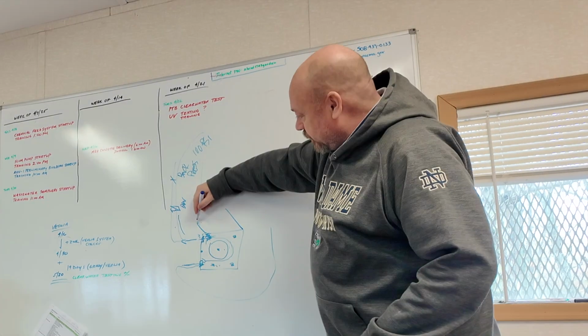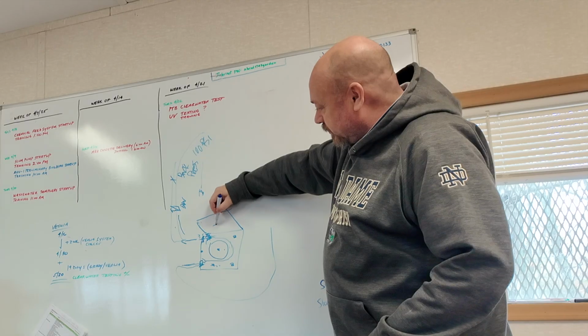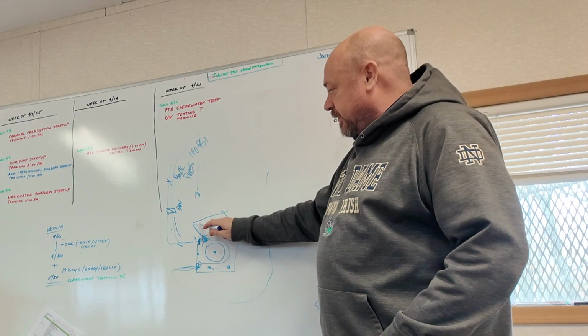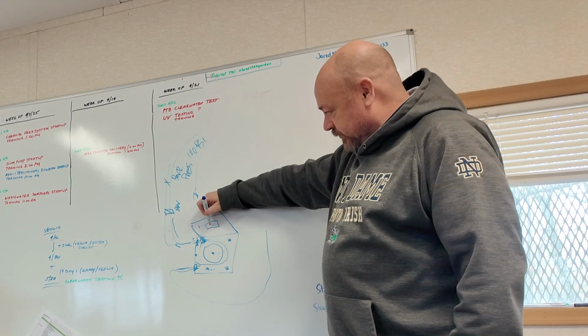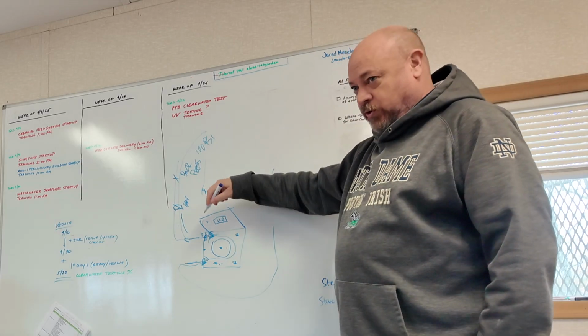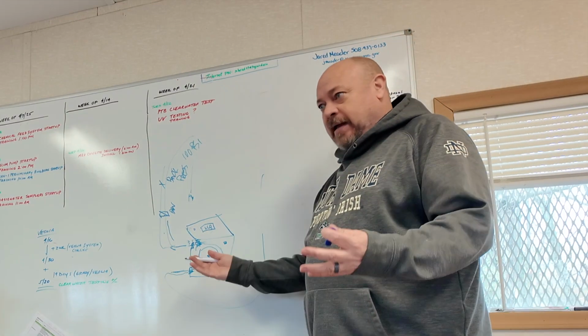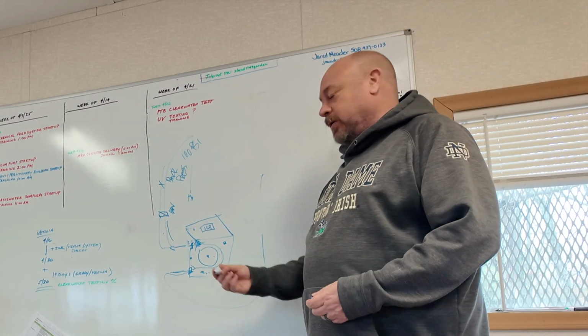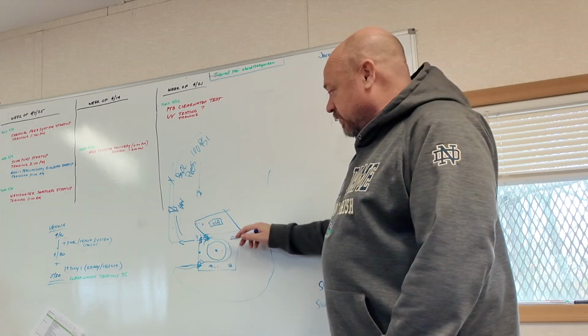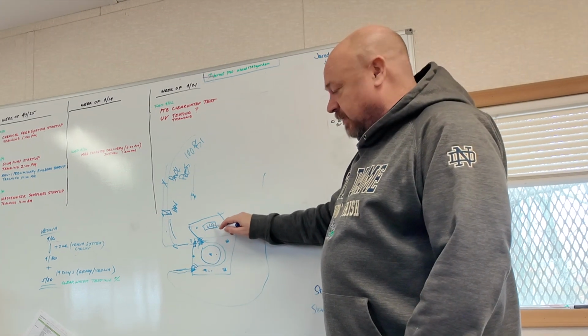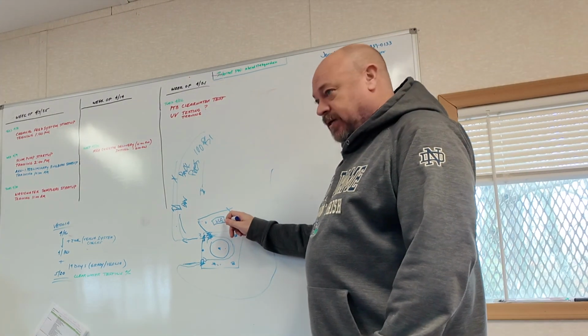Majority of the time, this is the top that controls. There's a screen on the top, and there's basically an on-off push button. This is an LCD screen, which we have set up so when you turn it on, it reads in gallons per hour. 90% of the applications are gallons per hour. If you want it to read in liters per minute, we can do that. So when this is running, you'll have the start-stop. You'll see that this is running at 10 gallons an hour, and you're pumping.